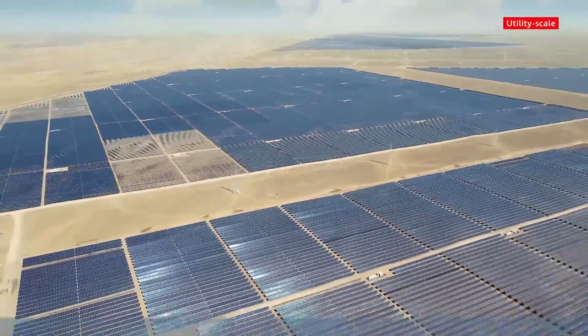The first solution is the FusionSolar 8.0 Smart PV Generator. Traditional PV generation is a supplementary generation unit. Going forward, to become the primary source of energy, PV needs to reduce the unit cost. It also has to be fully compliant with the most advanced technologies. To achieve that, we have developed the 1,500 volt bipolar smart string. This will help us achieve the synergy of PV and storage, the greatest efficiency, quick scheduling, and unified management. So this architecture can help PV stations reduce LCOE.